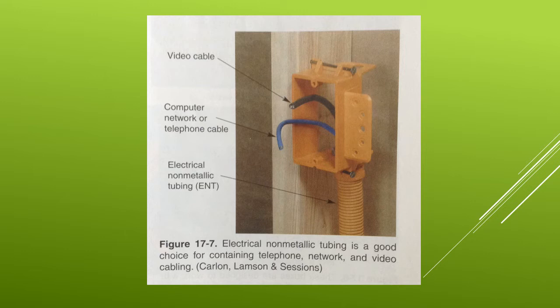Conduit. Installing conduit is a smart precaution against having obsolete cabling. Electrical and telephone wiring has not changed dramatically within the past few decades. However, manufacturers of computer cabling have consistently developed better performing conductors every few years. Replacing cables is much easier when conduit is installed.